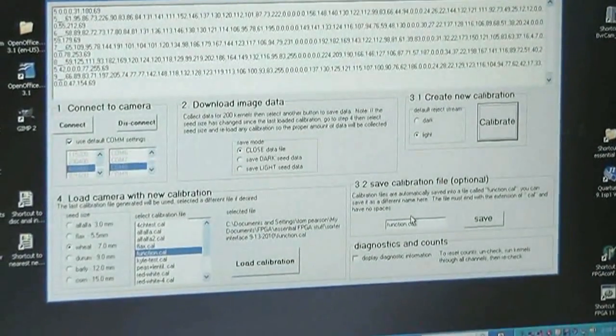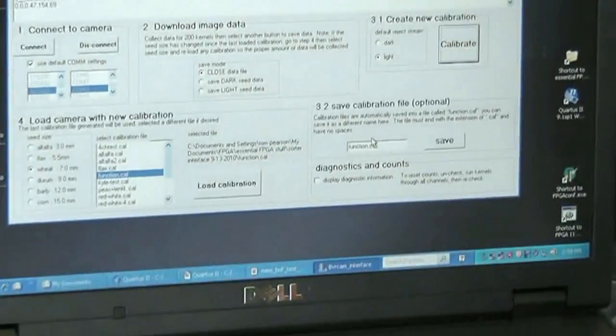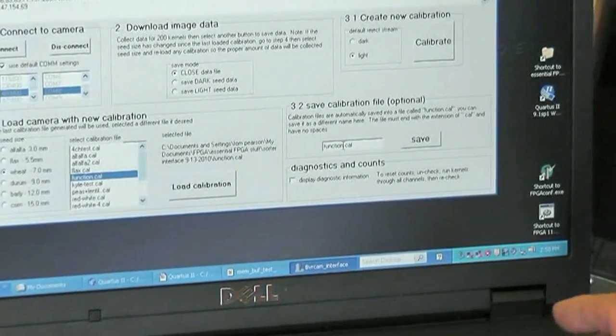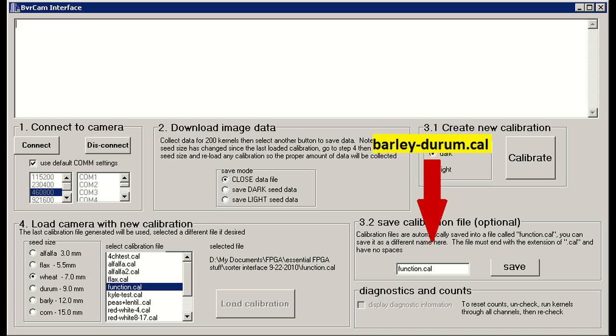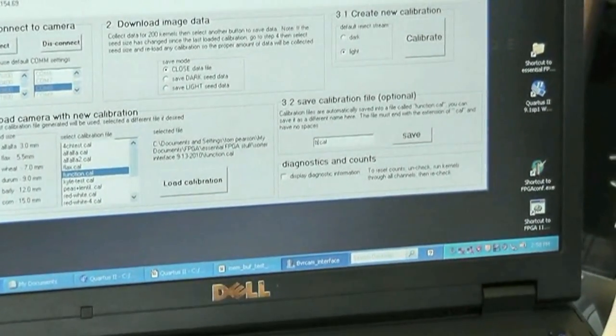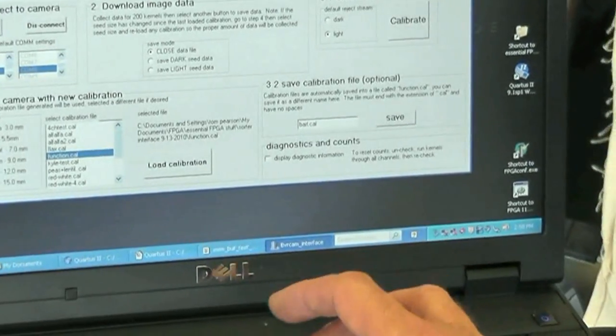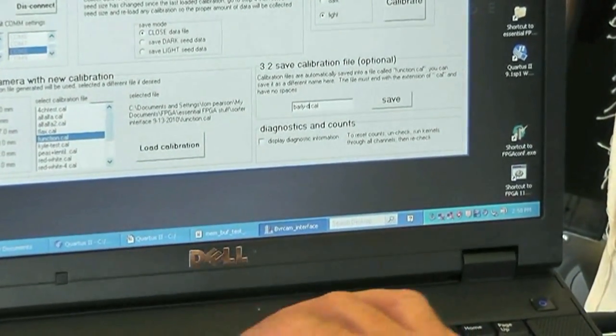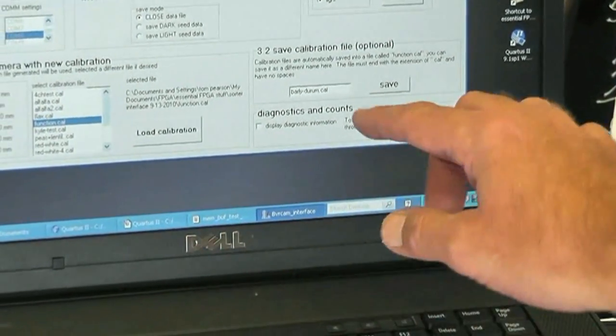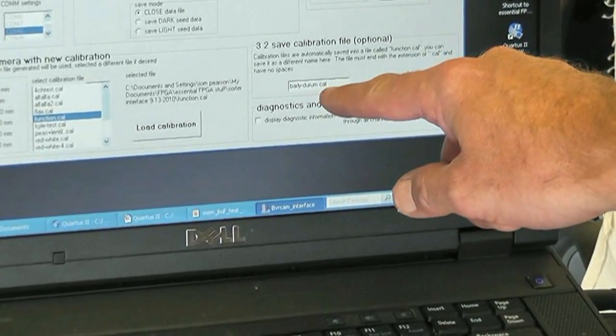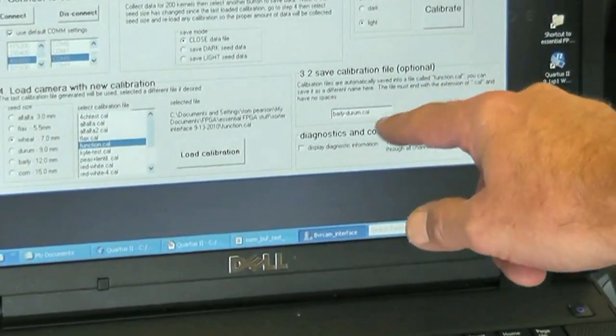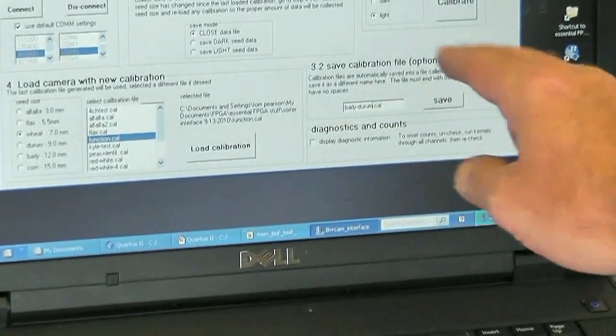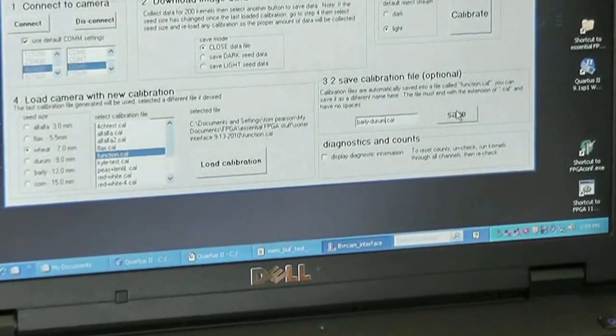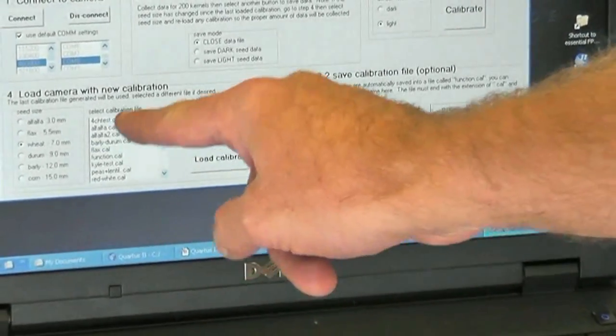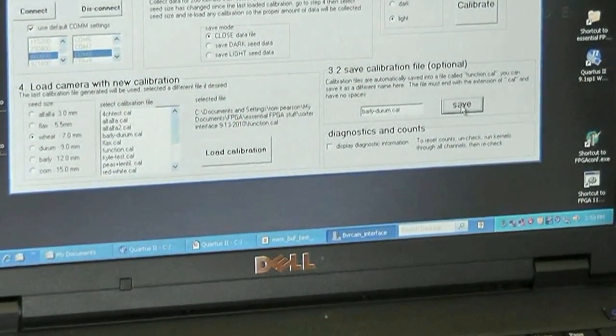It's done. And step 3.2, we can give this calibration file a name. We're going to call it barley-durum. And then you have to make sure that the .cal is still there. And you can't have any spaces in that name. And hit the save button, and that'll show up here in our available calibration files.